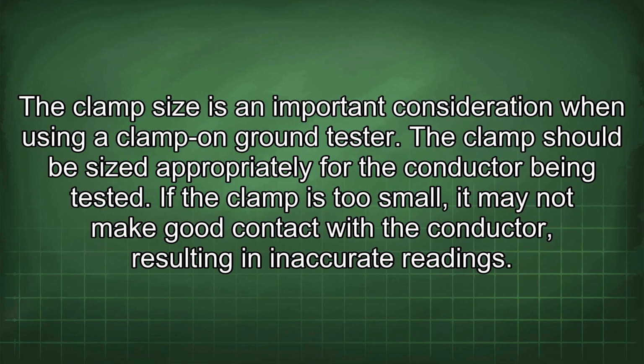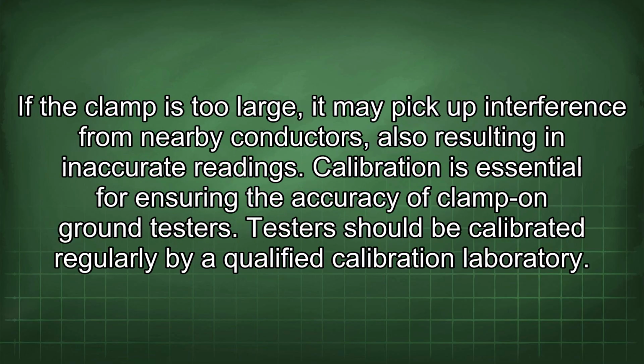The clamp size is an important consideration when using a clamp-on ground tester. The clamp should be sized appropriately for the conductor being tested. If the clamp is too small, it may not make good contact with the conductor, resulting in inaccurate readings. If the clamp is too large, it may pick up interference from nearby conductors, also resulting in inaccurate readings.